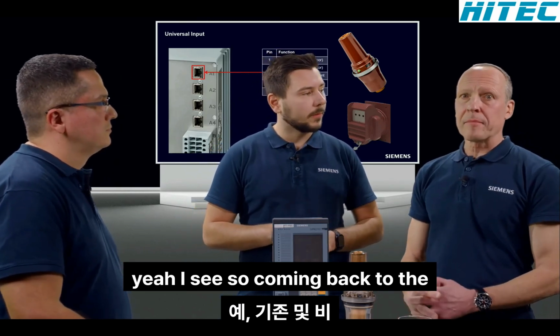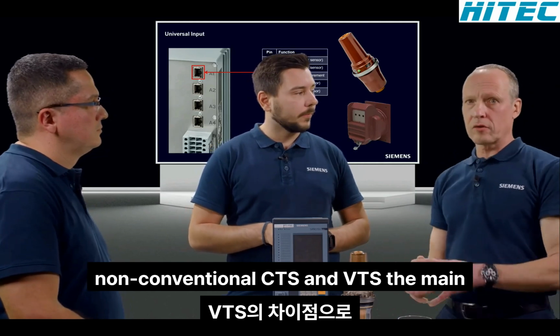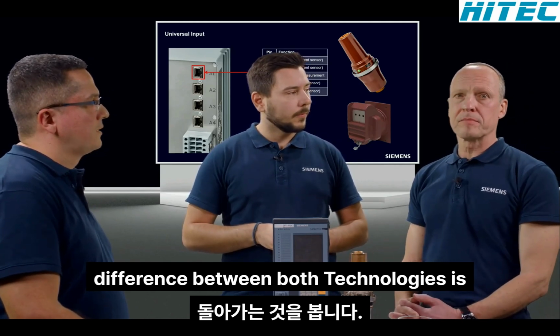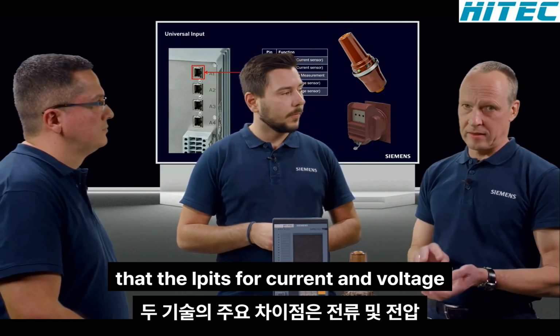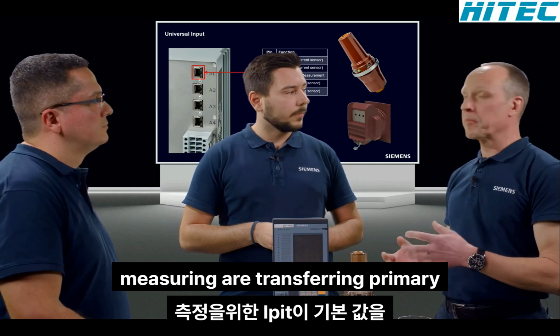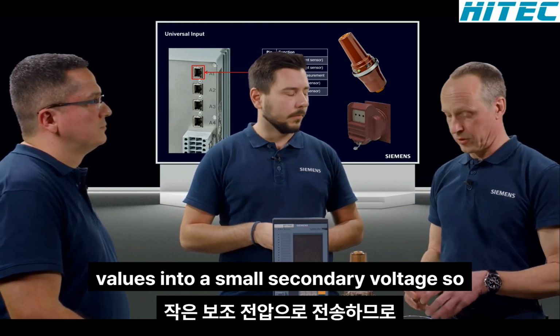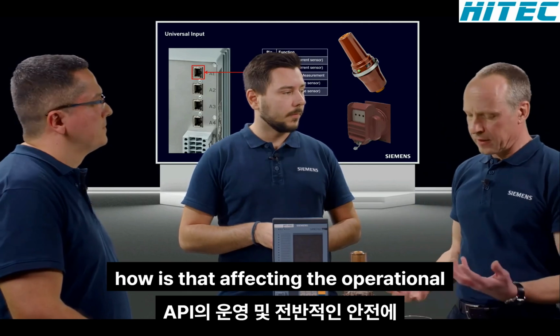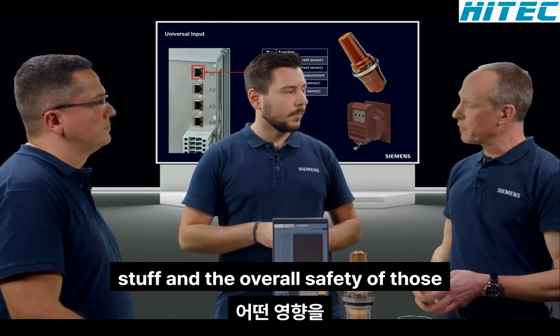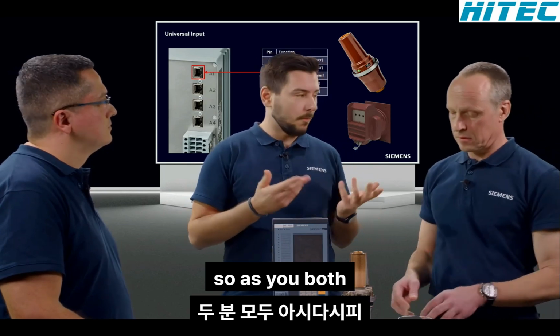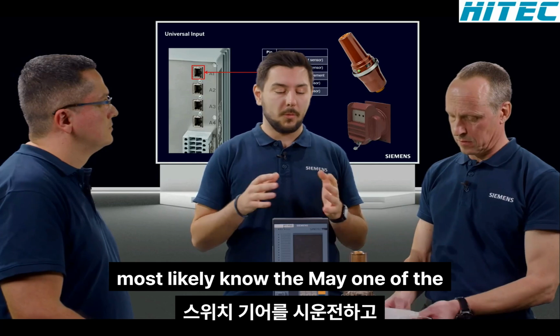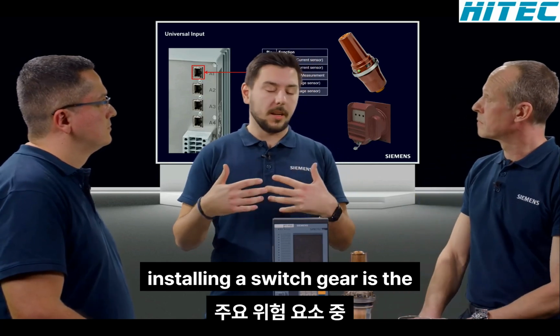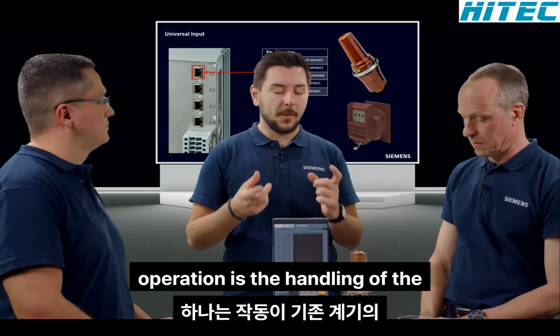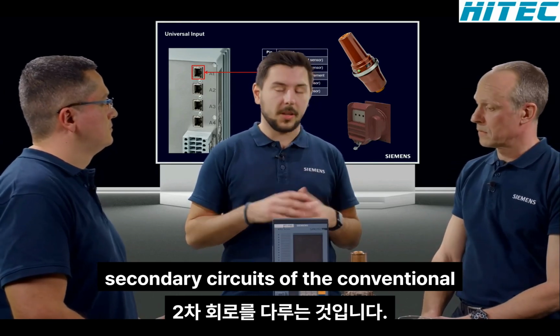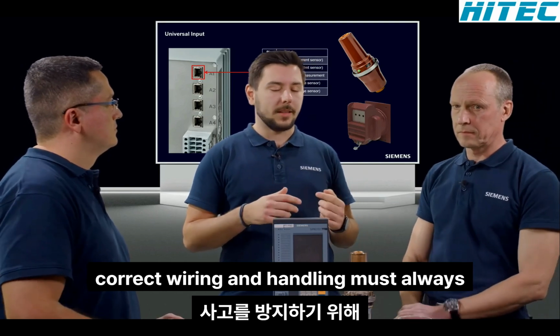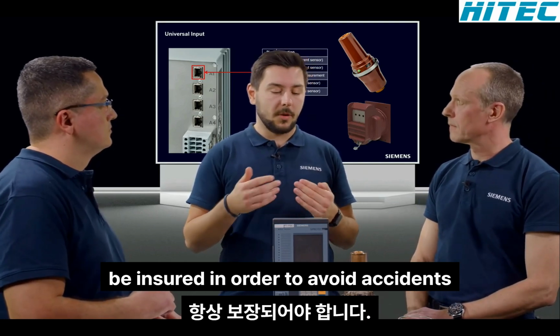Yeah, I see. So coming back to the differences between conventional and non-conventional CTs and VTs, the main difference between both technologies is that the LPITs for current and voltage measuring are transferring primary values into a small secondary voltage. So Lars, how is that affecting the operational side and the overall safety of those LPITs? So as you both most likely know, one of the major hazards during commissioning and installing a switchgear is the handling of the secondary circuits of the conventional instrument transformers. Correct wiring and handling must always be ensured in order to avoid accidents.